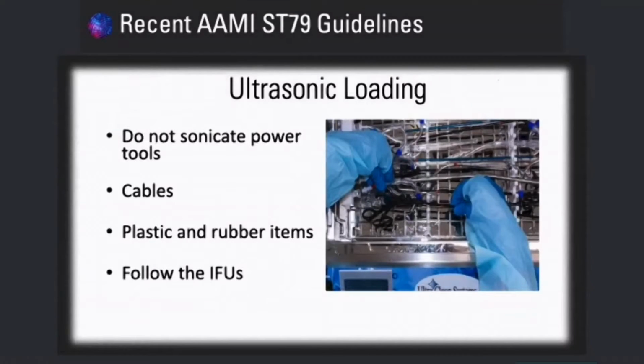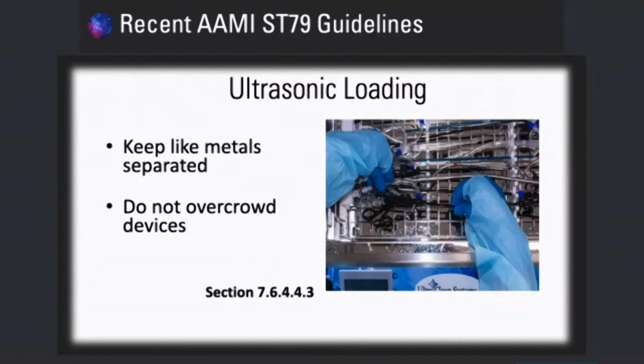Don't sonicate power tools, because they can't handle it; their motors can short and their cables can be leached with fluid, causing shorting. That's not a very good thing. Plastic or rubber items, like we mentioned, can impede sonication, so they can absorb the sonication, and therefore adjacent instruments can be affected and not cleaned as thoroughly. Follow the IFUs. Can't say that enough, right? I know you've heard it enough, but we just need to keep pounding that in.